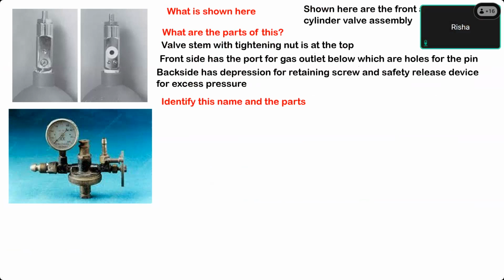This one, where does it go? So this has been removed from the hanger yoke assembly. Okay, this is the entry port. When you open this stem, gases will flow and enter through this, and the pressure gauge will show the pressure that is present in the cylinder.